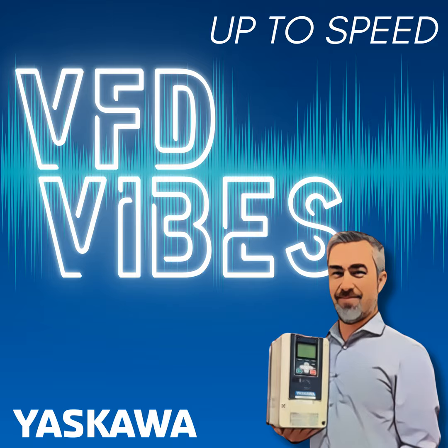Looking ahead, artificial intelligence, or AI, is beginning to play a role in preventative maintenance. Imagine a drive that analyzes trends in current, temperature, and bus voltage to predict failures before they happen. That future is coming and faster than most people think. I could see this being implemented a couple of different ways. Some of this could live directly in the drive, and some of this could live in that larger supervisory or SCADA system. So when your drive has that network connection and it's able to share its data and its monitors with that system, the system can use its own AI to characterize that drive, know what it should be running like in normal conditions, and tell you when things start to differ from the norm. I think this will be a really cool future.